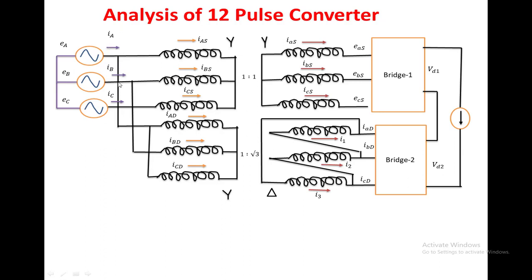Phase a, phase b, and phase c currents are supplied by the supply. If we take the phase b current, that is equal to the sum of the phase b current in the star-to-star transformer and the star-to-delta transformer. In the same manner, ia, ib, ic are the currents supplied by the sources, equal to ia_s plus ia_d; ib_s plus ib_d; ic_s plus ic_d.